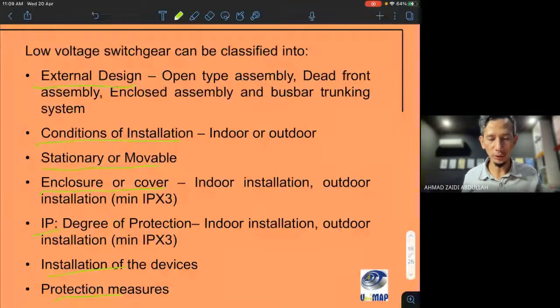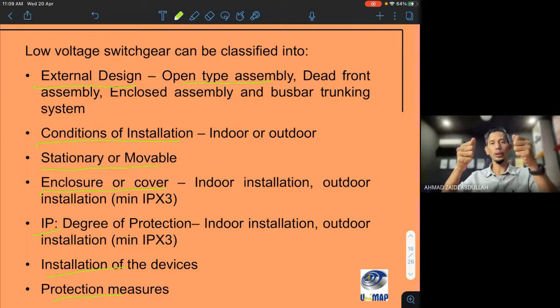So external design depends on the open type assembly. So this is the MSB, or whatever type of switchboard, MSB, SSB, LDB. How do you open the assembly? You can open it from the front like this, or you can open from the back door, or I said dead front assembly. Dead front means the front area cannot be opened. If you want to make a connection and so on, you need to go to the back door of the switchgear. And then how the busbar trunking system is inside.